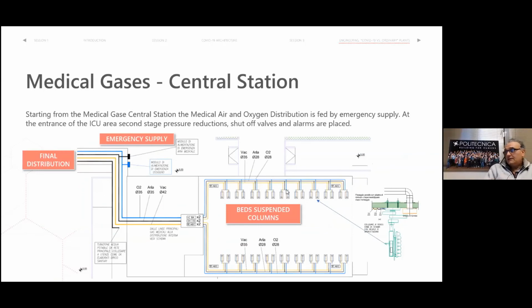Okay, this is an example of the distribution scheme. The central stations are located here on the left, elsewhere. We will provide emergency supply because you cannot stay without gas. It is impossible. So if you have problems, you must call the cylinder truck, and then connect it immediately, the emergency for medical air or oxygen, if it is necessary.